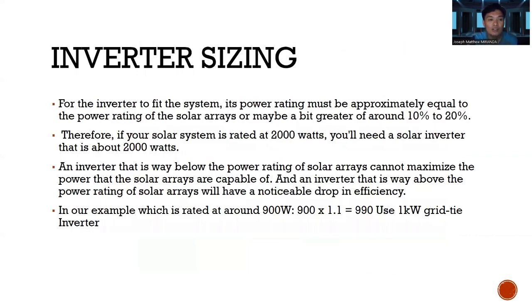So next tayo. Inverter sizing. For the inverter to fit the system, its power rating must be approximately equal to the power rating of the solar array, or maybe a bit greater by around 10% to 20%. Therefore, if your solar system is rated at 2000 watts, you'll need a solar inverter that is about 2000 watts. An inverter that is way below the power rating of the solar arrays cannot maximize the power that the solar arrays are capable of. And an inverter that is way above the power rating of the solar arrays will have a noticeable drop in efficiency.